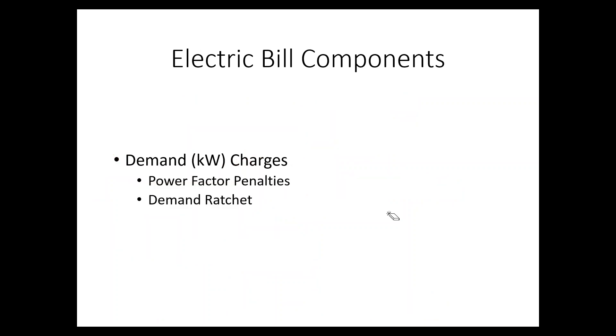Demand charges are typically composed of a couple of items. One is power factor penalties, which is a penalty for the power quality that your facility influences back to the grid — we'll cover that in another section. The other is the demand ratchet, which means that if you use a lot of power at one time and then don't use energy, they still charge you. We'll cover that in another section as well.